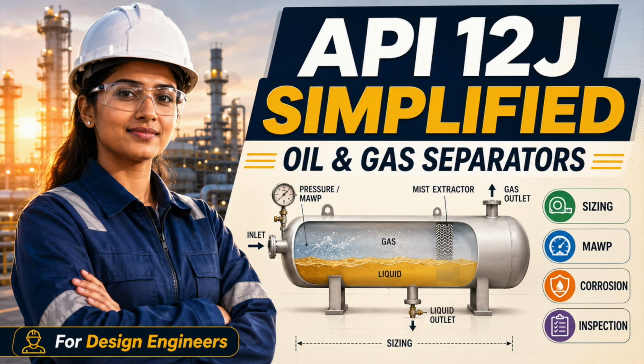Now look at level control. The liquid level is the operating heart of the separator. If the level rises too high, you lose gas disengagement volume and risk liquid carryover. If the level falls too low, you risk gas blow-by through the liquid outlet. Both events can become serious. Gas blow-by may overpressure downstream equipment, disturb pumps, create flashing, vibration, and unsafe conditions.